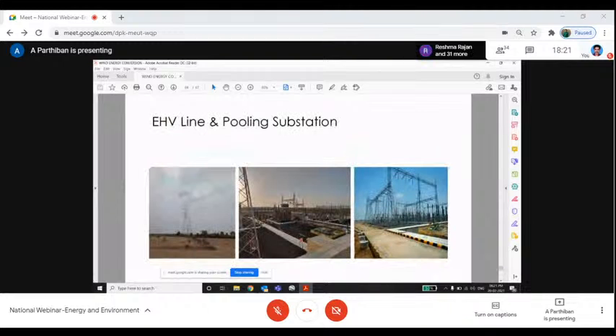All these wind turbines have been connected through a 33 kV network, and it is further connected to the pooling substation, in which all these 300 megawatt will be pooled at the 33 kV level. And from the pooling substation, the 33 kV level is stepped up to 230 kV level, and further it is transmitted to the grid substation through EHV lines. These EHV extra high voltage lines are also constructed by developers, and they connect with the grid substation. From there, the distribution network will start.